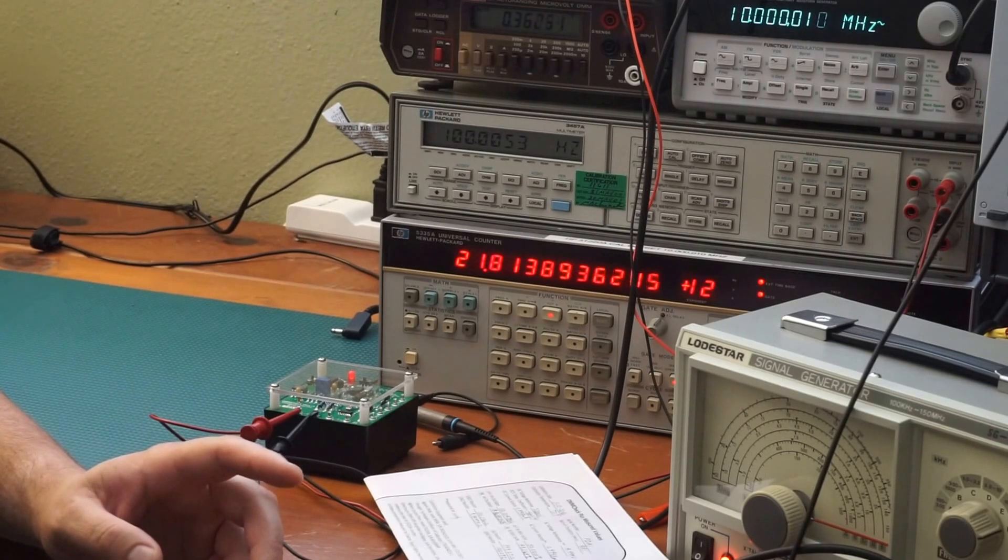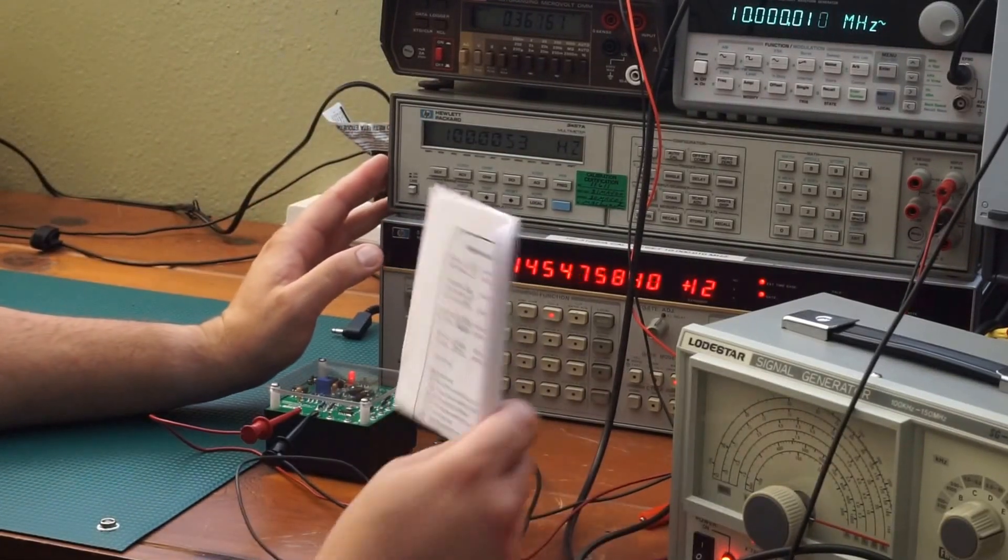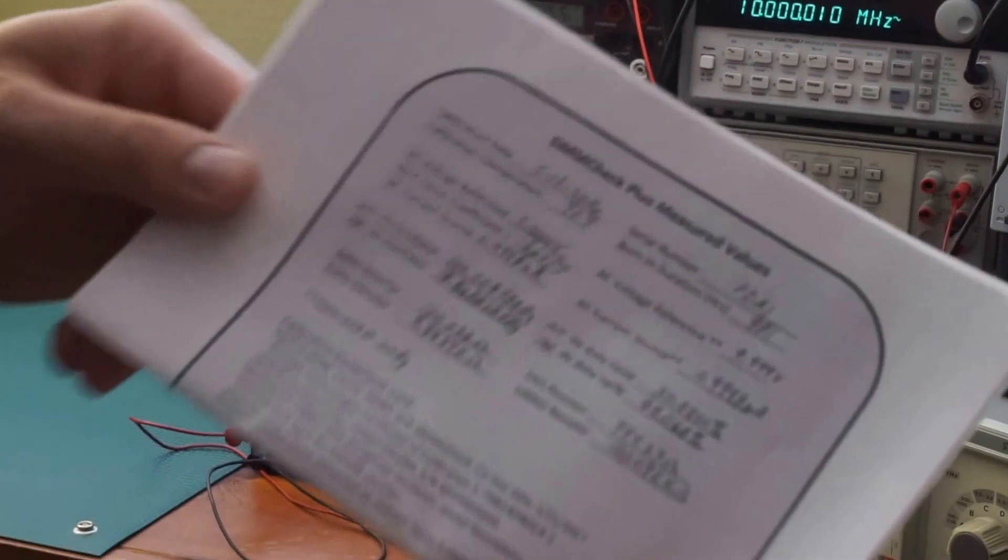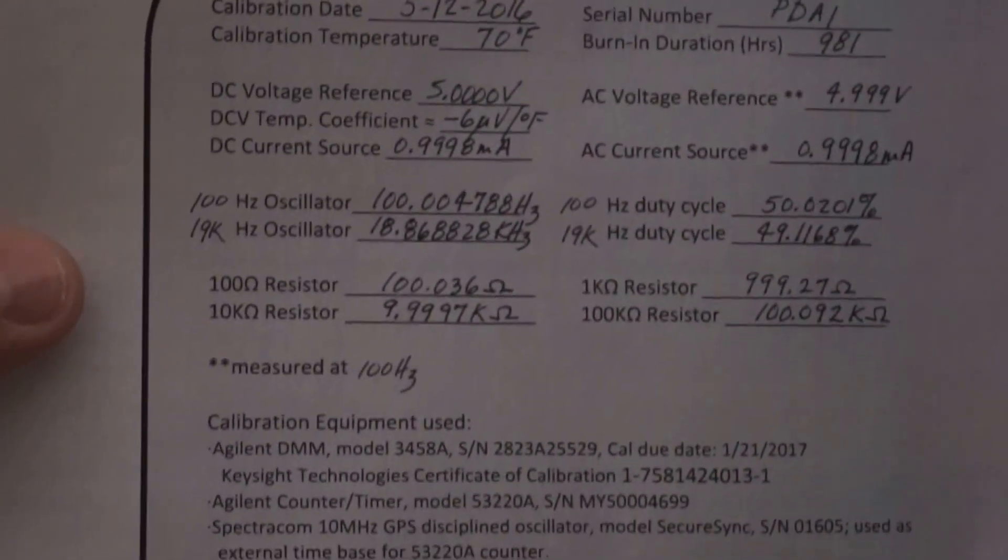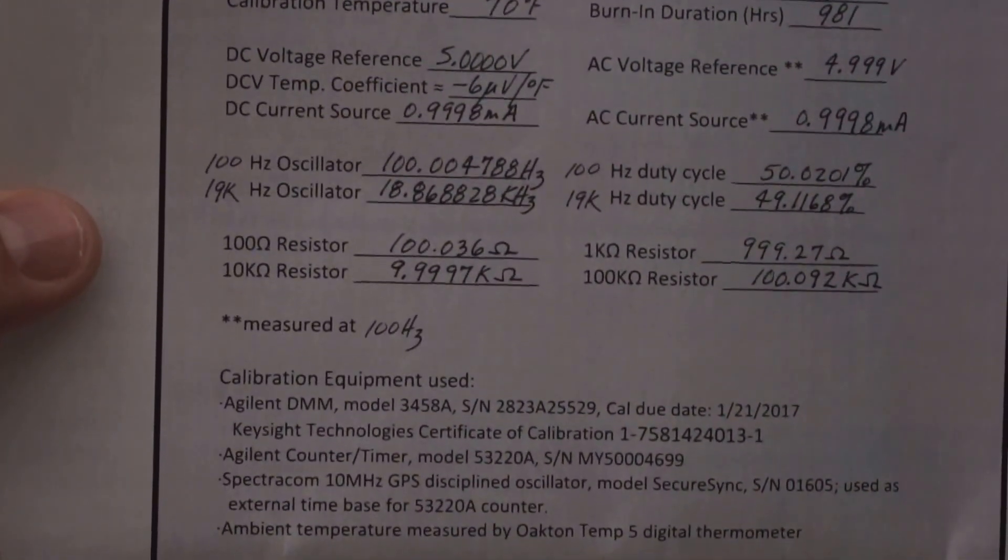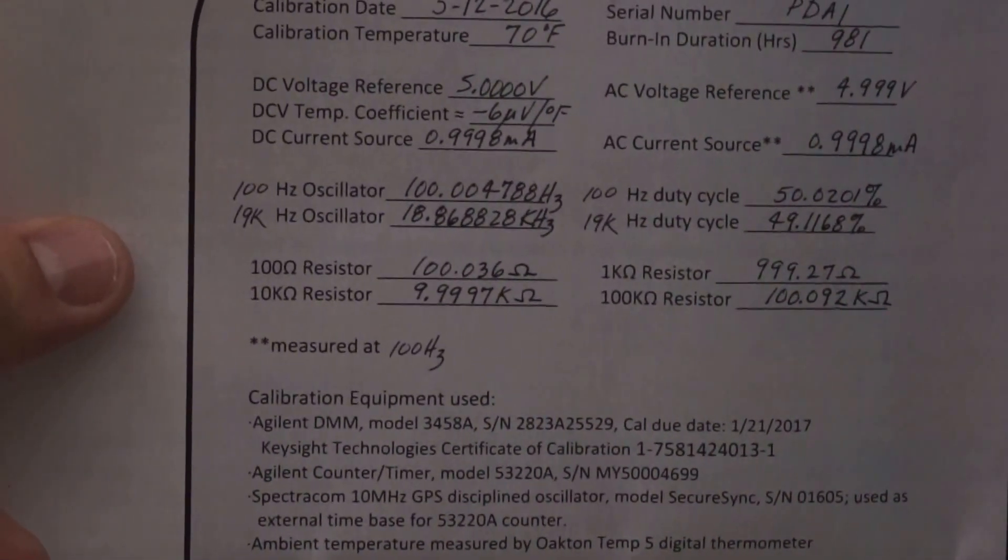So I purchased the DMM check plus model that offers two different frequency ranges and I think it's a $10 extra feature. I chose 100 Hertz and 19 kilohertz. Right now we're at the 100 at the 100 Hertz range and my multimeter is reading 100.0053 Hertz and let me show you what they send me here. They sent me. So as you can see it's 100.004788 Hertz so it's right there.